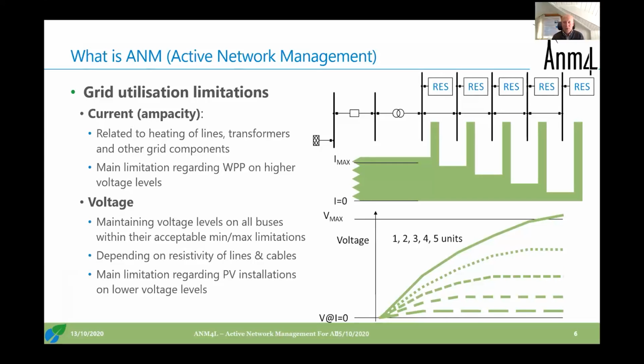Grid utilization limitations can be seen from two perspectives. There's the bottom-up perspective, where we have ampacity limitations in the grid relating to heating, as we just heard. Many components can be a limiting factor in this system, but the summing up of currents from distributed resources results in limitations that can be identified in different places in the grid, coming from the bottom up.